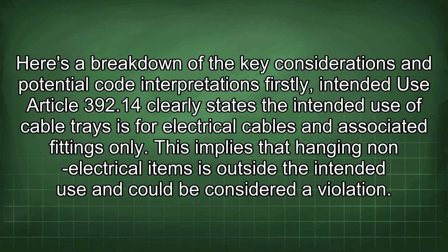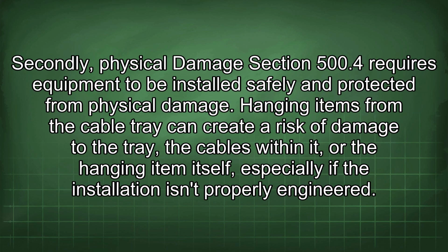Here's a breakdown of the key considerations and potential code interpretations. Firstly, intended use. Article 392.14 clearly states the intended use of cable trays is for electrical cables and associated fittings only. This implies that hanging non-electrical items is outside the intended use and could be considered a violation. Secondly, physical damage. Section 500.4 requires equipment to be installed safely and protected from physical damage. Hanging items from the cable tray can create a risk of damage to the tray, the cables within it, or the hanging item itself, especially if the installation isn't properly engineered.